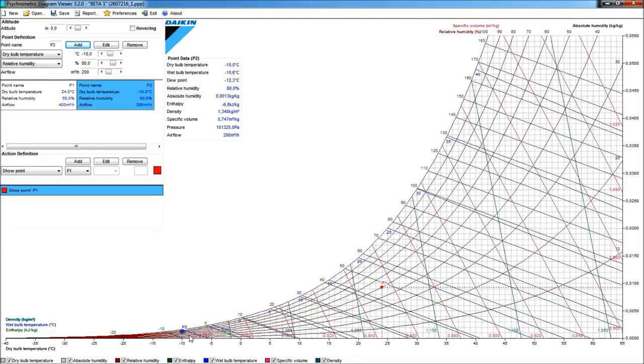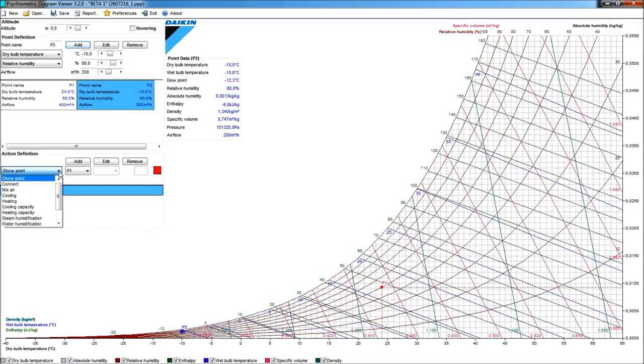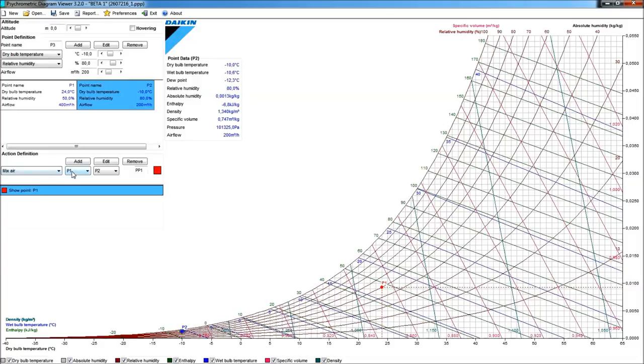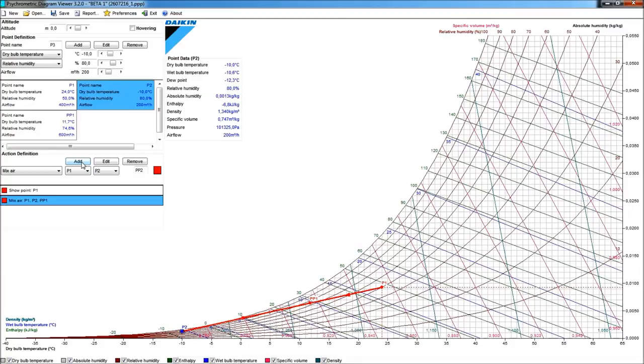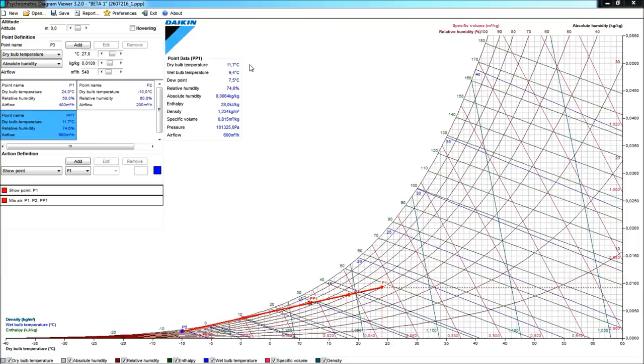Now, what, of course, I would be interested in is to know where about the mixed condition of these two air volumes would be. So, as a next action, I could ask here from the pull-down to see the mixed air condition between point P1 and point P2. Now, obviously, when I click Add here, I will draw that line, and somewhere on that line my mixed air condition will be the condition in point PP1. I see that it has a dry bulb temperature of only 11.7 degrees centigrade. So, this is a condition that would be far too cold to introduce into my room.